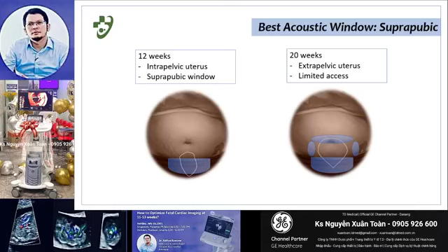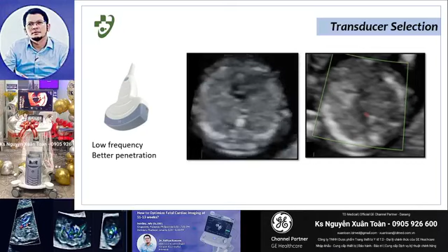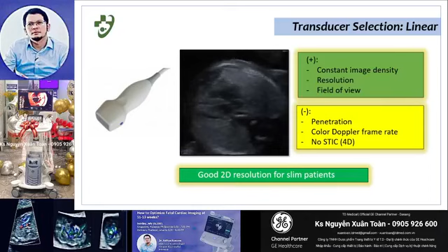Firstly, I'm going to talk about how we choose the probe. This is a probe with a low frequency and better penetration. This is good for obese patients. And for the linear transducer, this is good for resolution, field of view, and constant image density. But the downside of this probe is that the penetration is not that good for obese patients, and the color Doppler frame rate. We can't use STIC 4D with this probe. This is very good for slim patients.